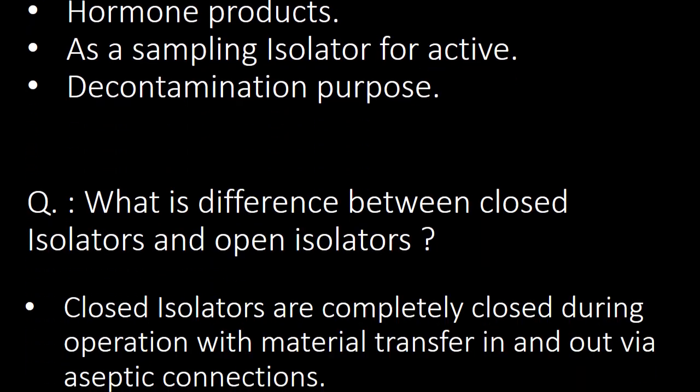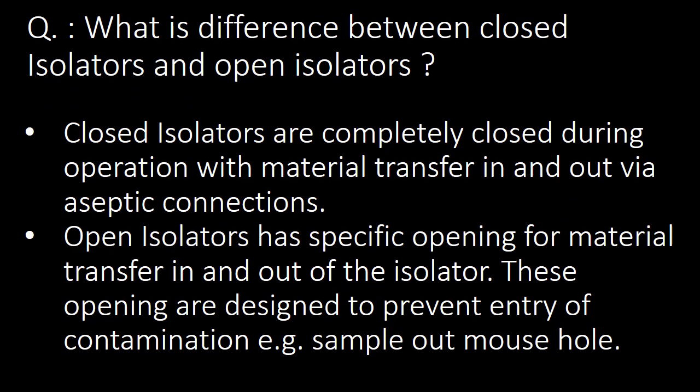The next question: what is the difference between closed isolators and open isolators? Closed isolators are completely closed during operation, with material transfer in and out via aseptic connections. Open isolators have specific openings for material transfer in and out, designed to prevent entry of contamination — for example, sample-out mouse holes.